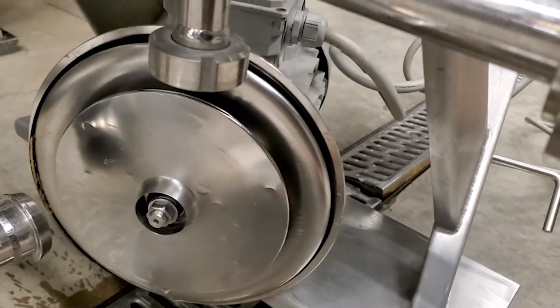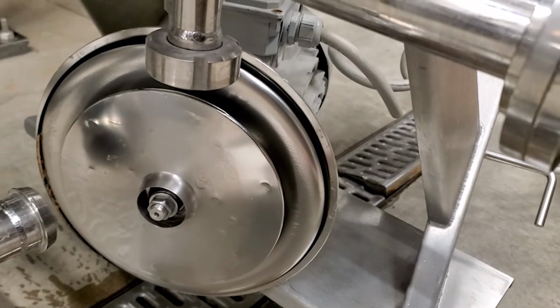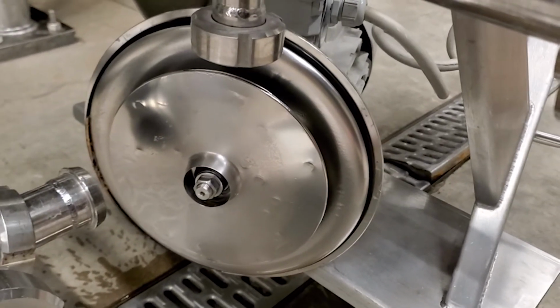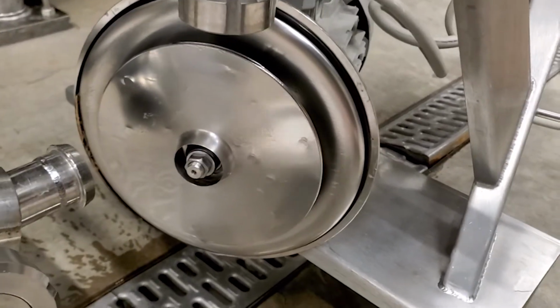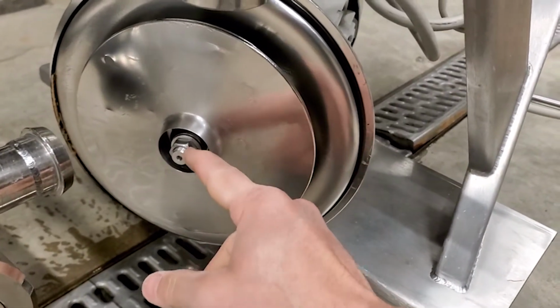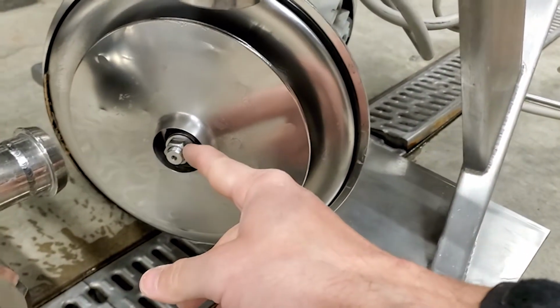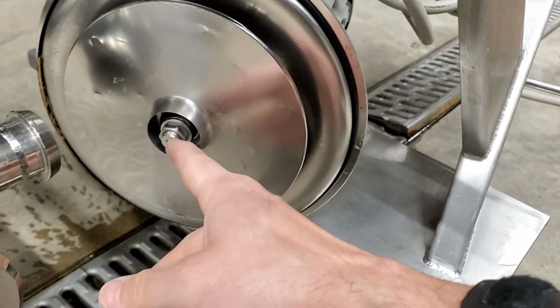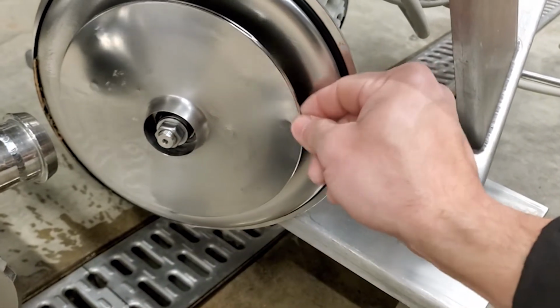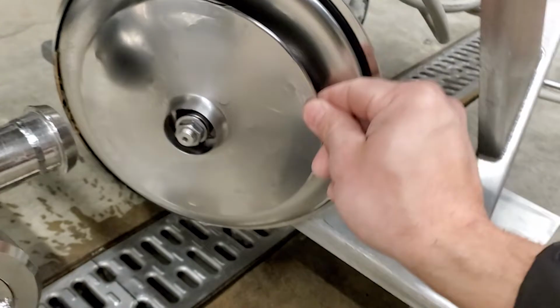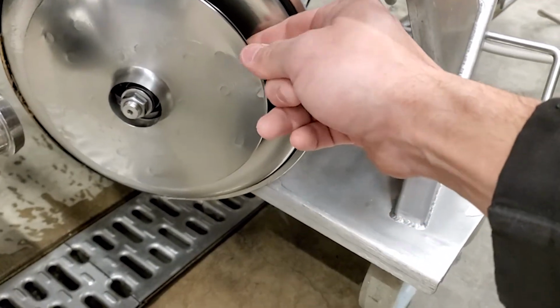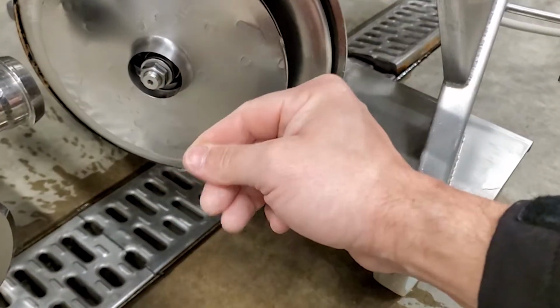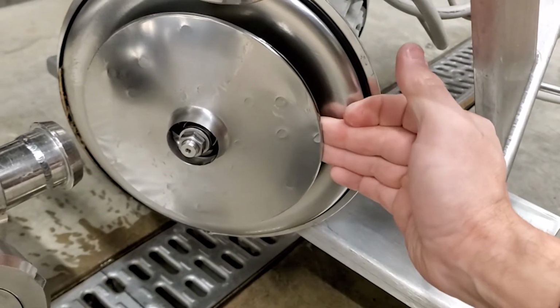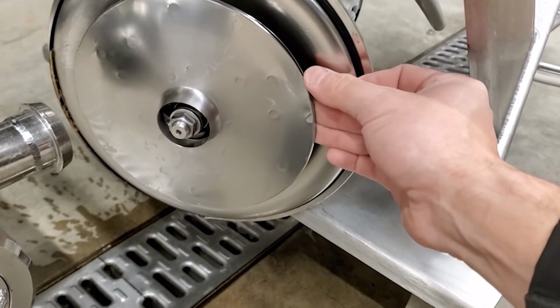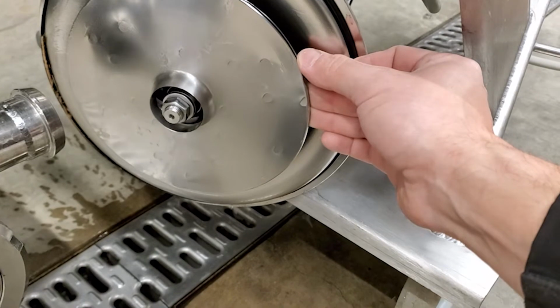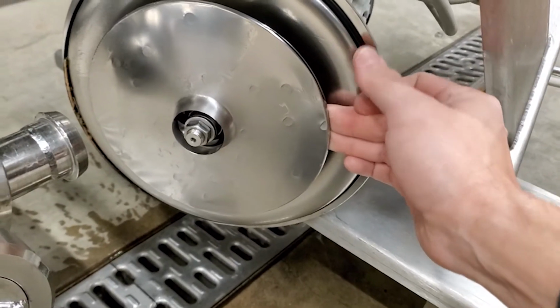Now we see the actual pump. We're going to pull that pump out, set it on the back side of the motor, and remove this nut here. Sometimes that nut is just a huge pain to remove. It's what holds this impeller on there. So we're going to remove that, pull this plate off, which is another huge pain, and then replace that seal.